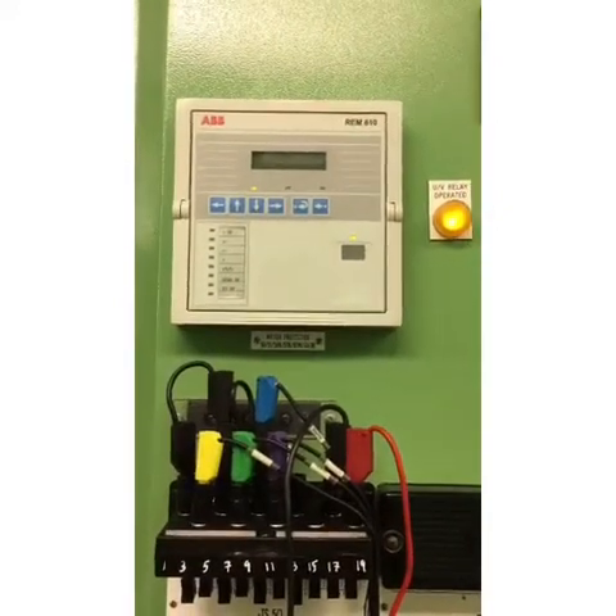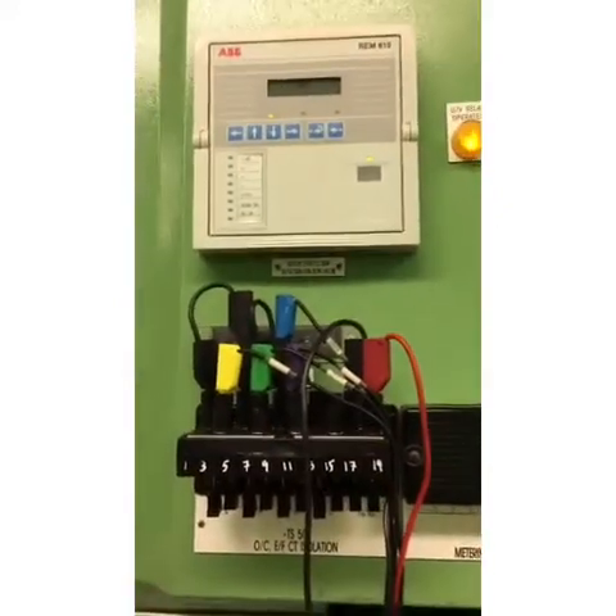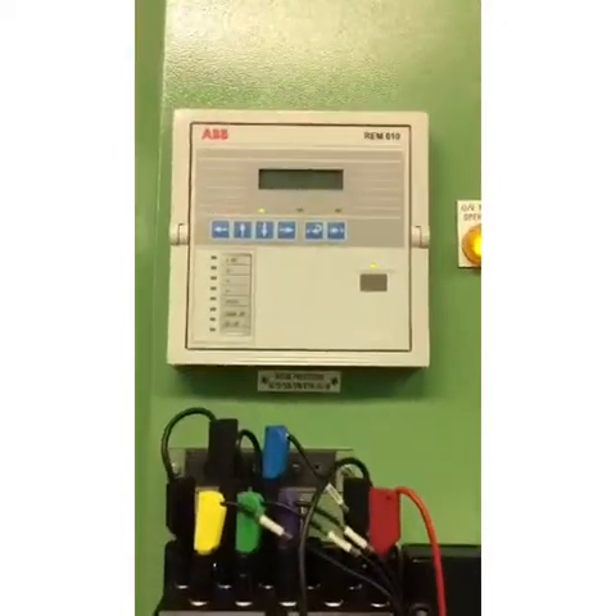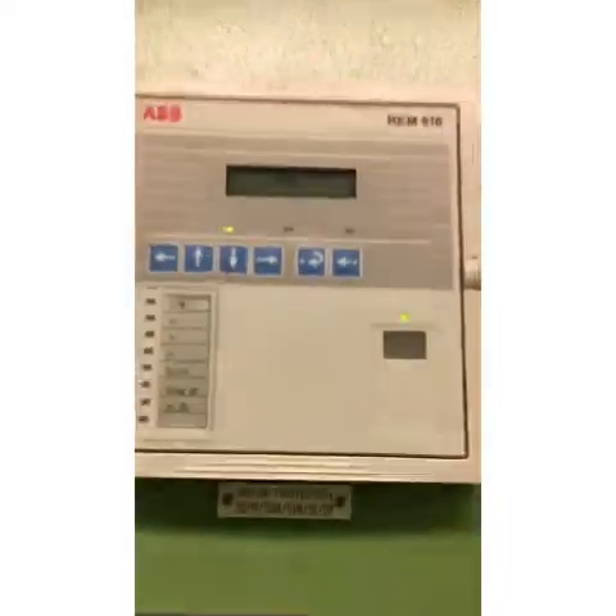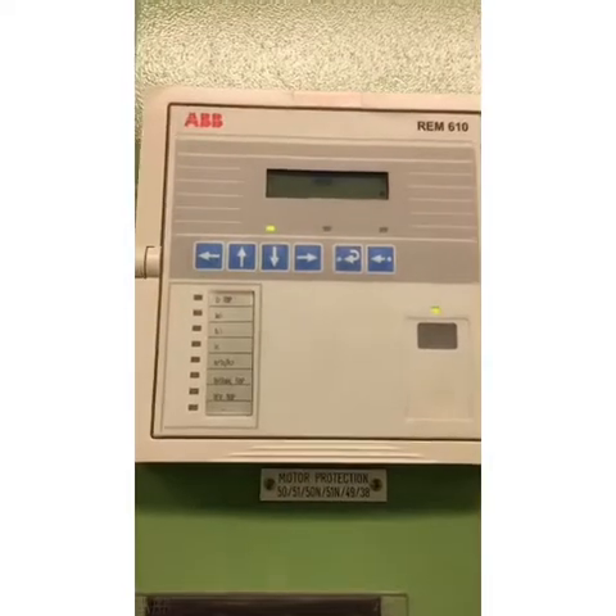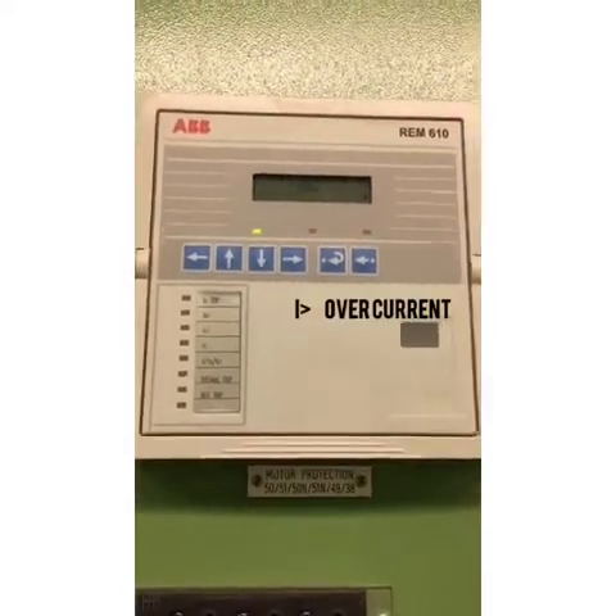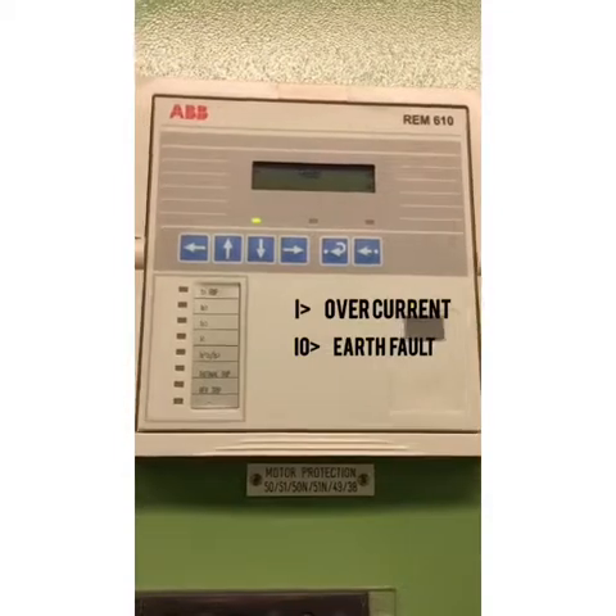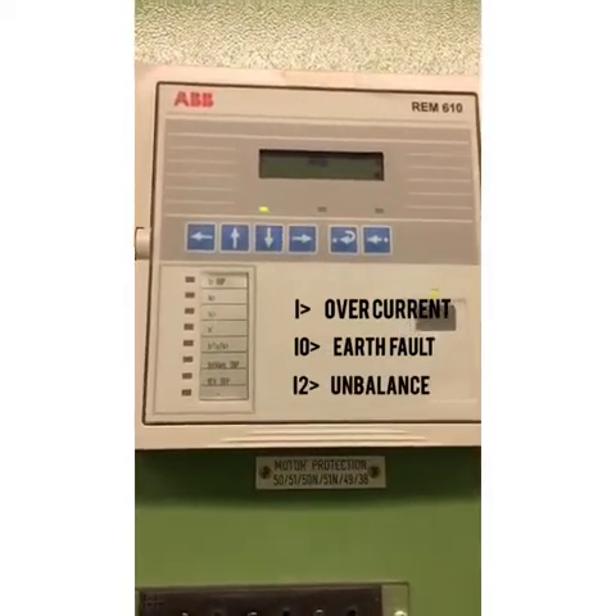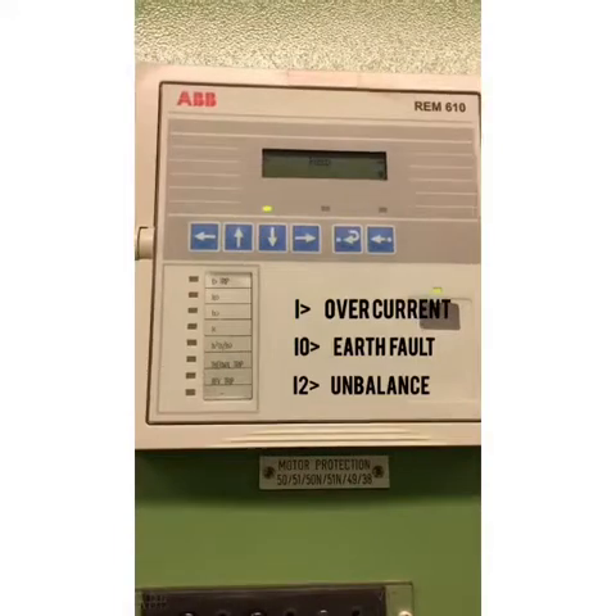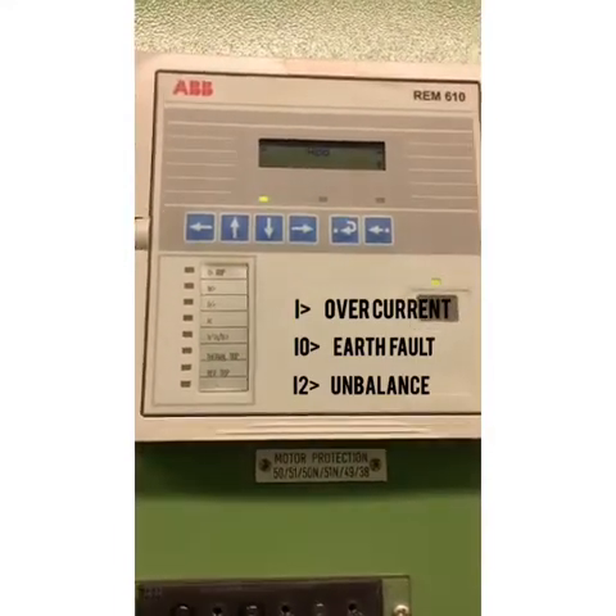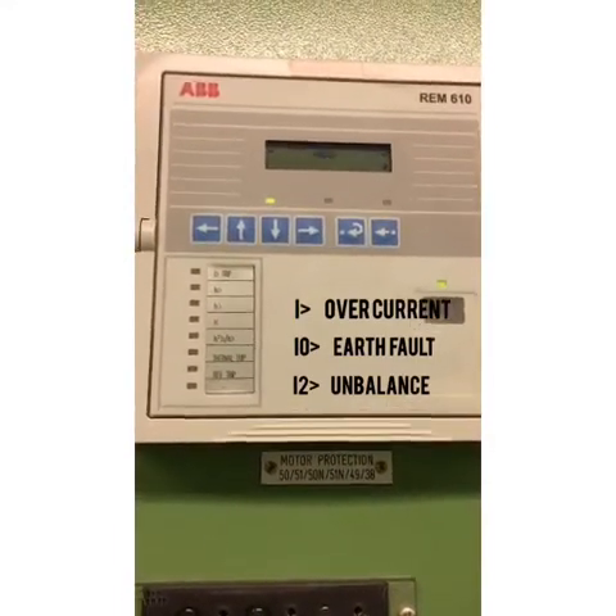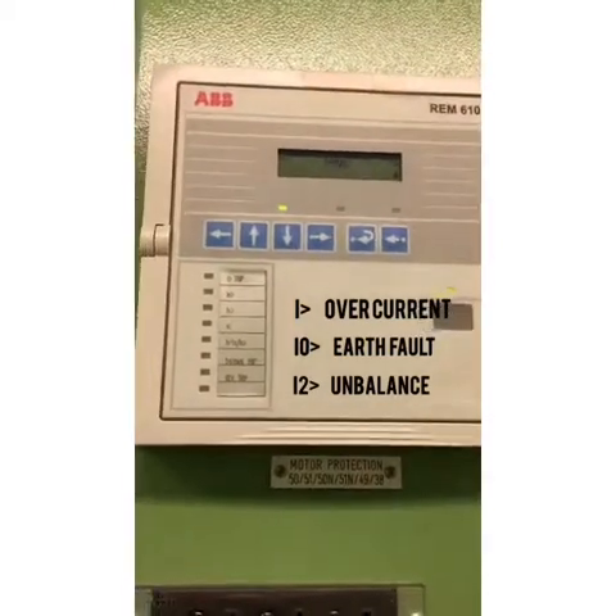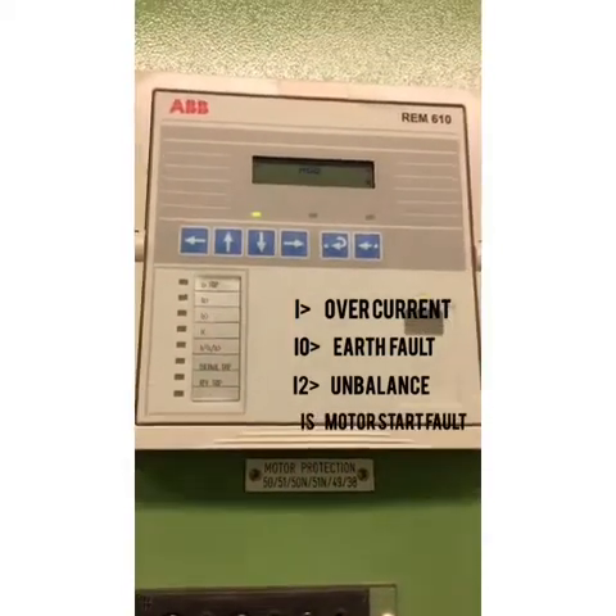As long as we are in annual inspection, I have the chance to give a fault signal. I will give fault current. We will read together what the fault is. But first of all, let me share with you what kind of protections we have here. The functions we usually have for REM are overcurrent, earth fault and imbalance with its types like broken phase or unbalanced current between the phases, and we have the motor start, and we have thermal overload.